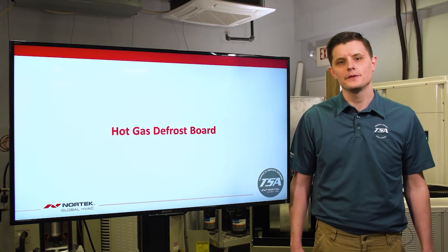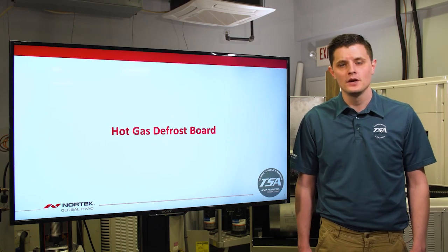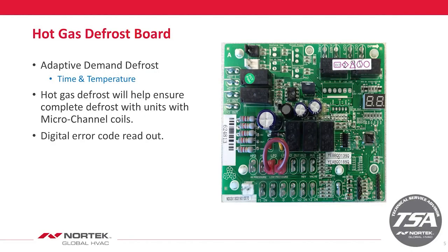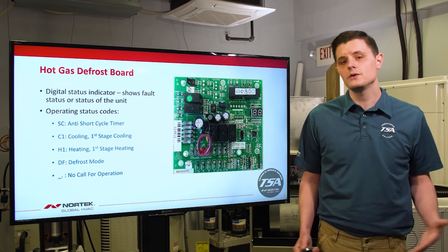The hot gas defrost board will be found on our two-stage and single-stage pieces of equipment. This board is categorized as our adaptive demand defrost board, meaning it takes into account run time and temperature inputs to determine when the unit will go into defrost. Hot gas defrost will ensure complete defrost with units with micro channel coils. We also have a digital readout to help ensure proper diagnosis and give you codes on your unit operation. The digital status indicator will show faults and operating codes.